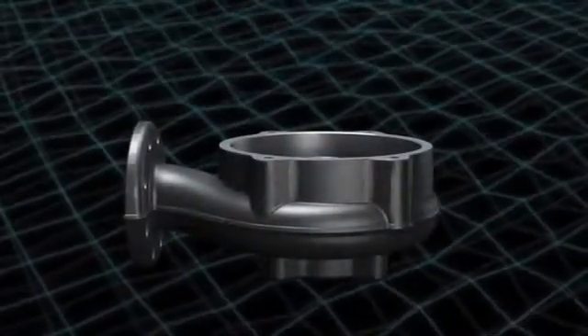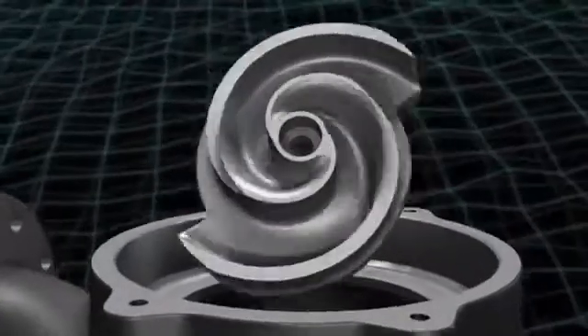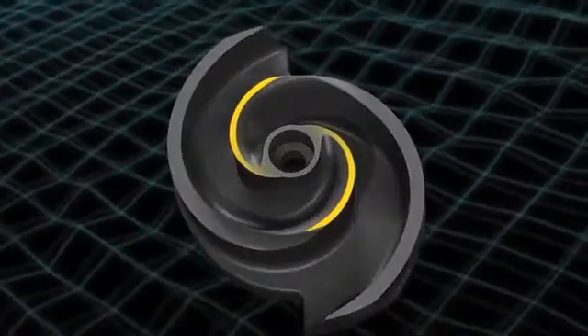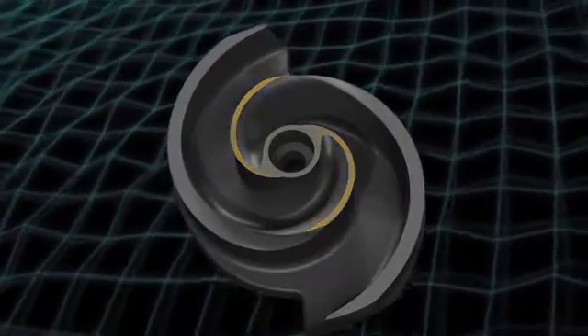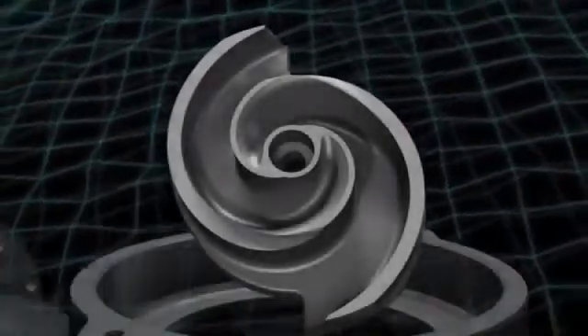It starts with a state-of-the-art impeller and volute that are specifically configured to process solids more easily and reduce clogging. The IMPACT impeller has a swept-back leading edge design that allows debris to pass through easily and a rib vane on the back shroud of the impeller, serving as a second line of defense for stringy material.